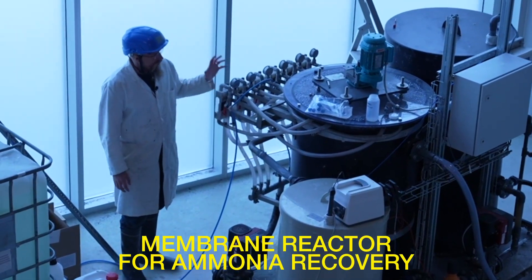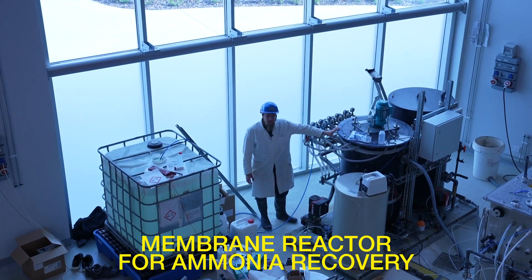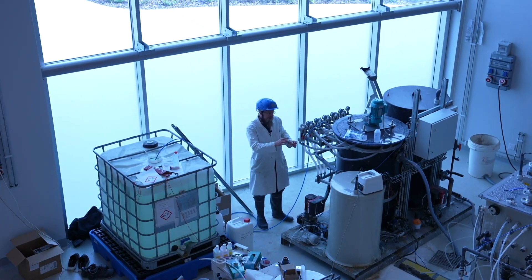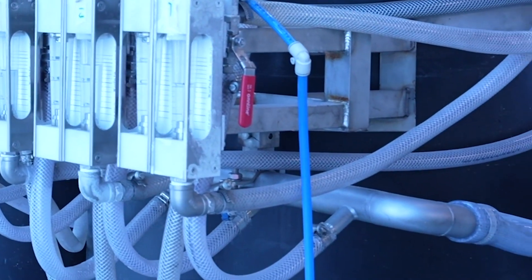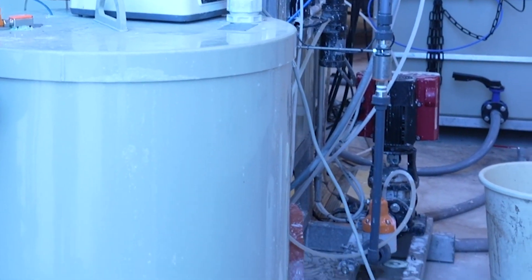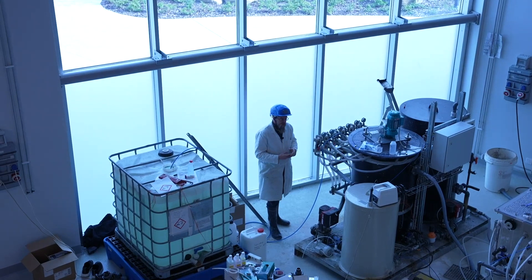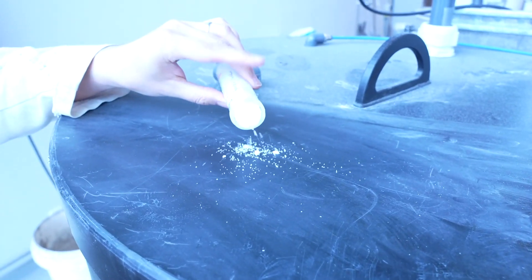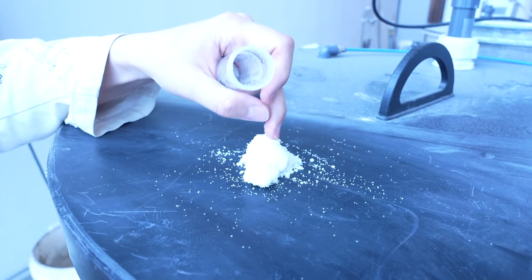This module is the ammonia recovery reactor. This tank contains six modules; each module has membrane fibers, and there's an acid that flows inside those fibers. The ammonia that is now volatile — thanks to the pH increase — goes through those membranes, reacts with the acid, and forms ammonium salt, which is a high-quality product. So what we had in the beginning — pee and poo — now becomes a high-quality white crystal when dried, which can be used as a raw material for fertilizers or any other industry that needs ammonia in their process.